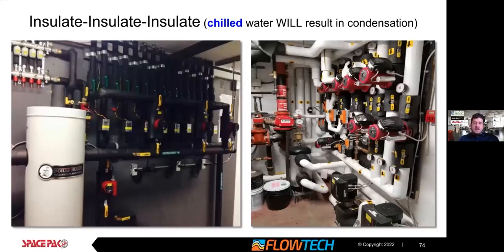Insulate. Often folks insulate for energy efficiency, but with the chilled water, we're insulating for condensation control, and it's different, right? So you really have to go back, and you think you've insulated it well. You can see this one on the left, hey, that looks pretty good. Well, every one of these stems is going to drip. This manifold is not insulated. The pump here. So there are areas where even if it looks good, it is not. So it's very important to insulate well.